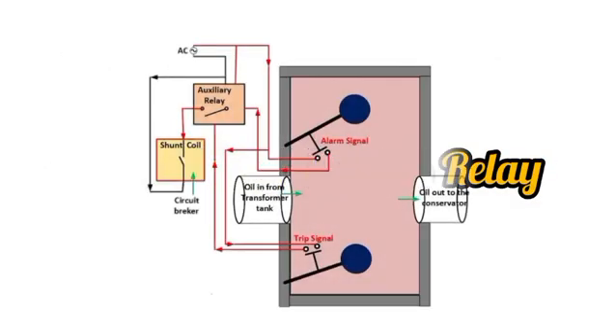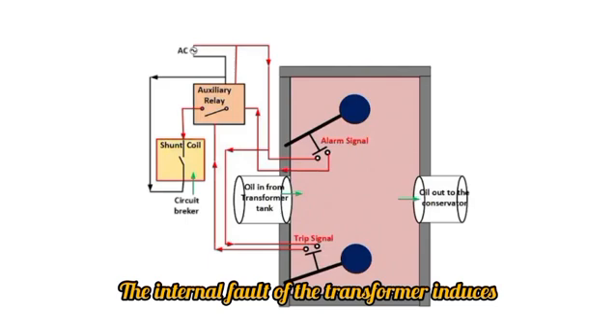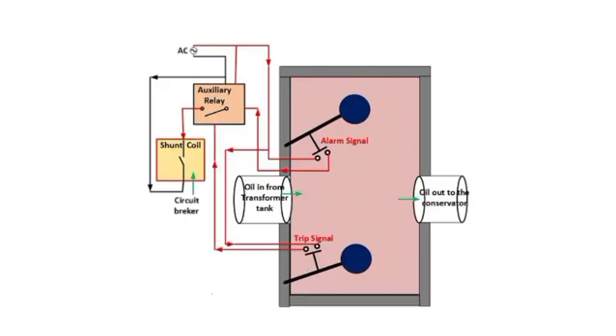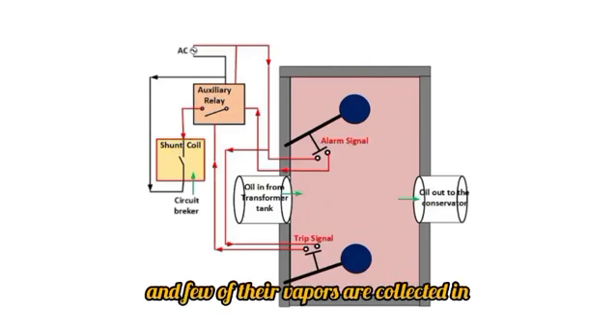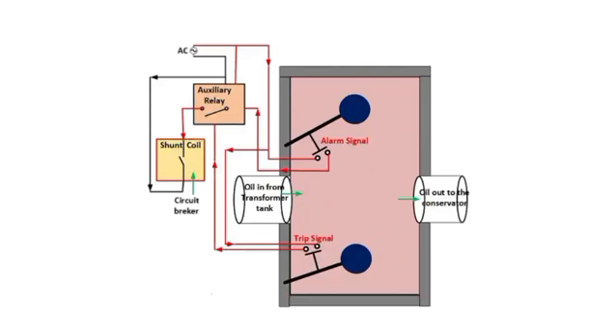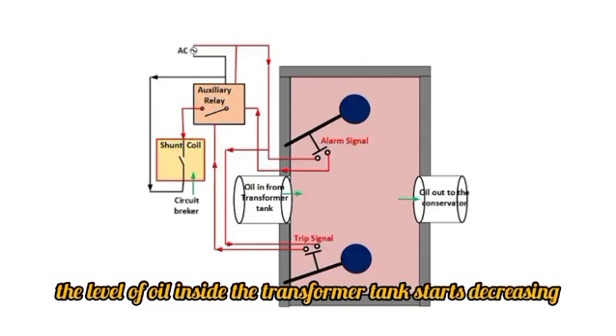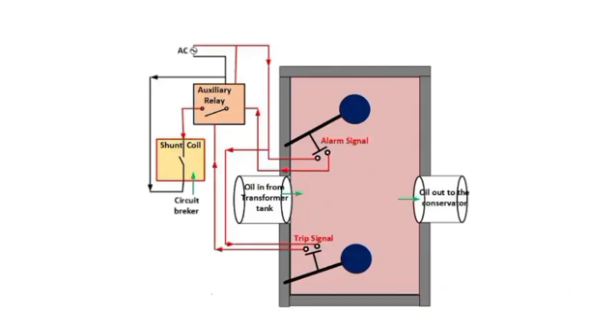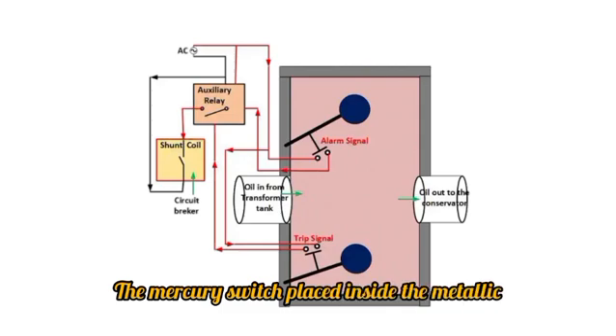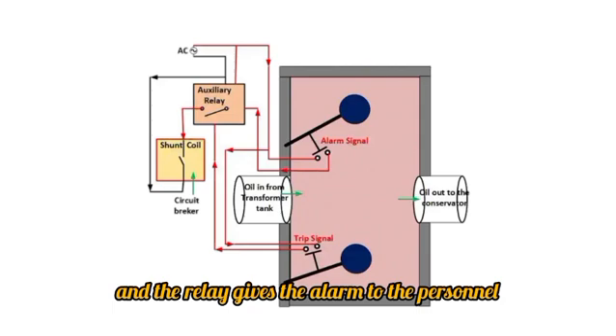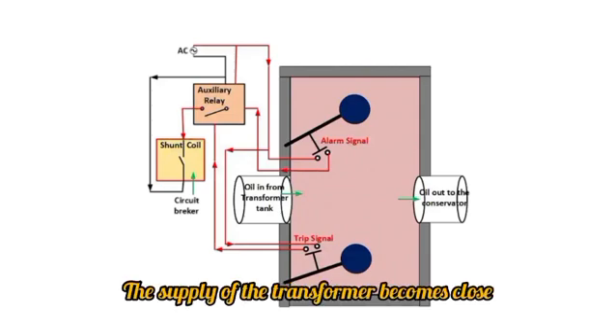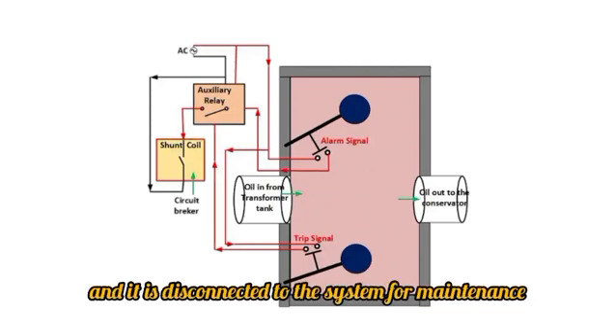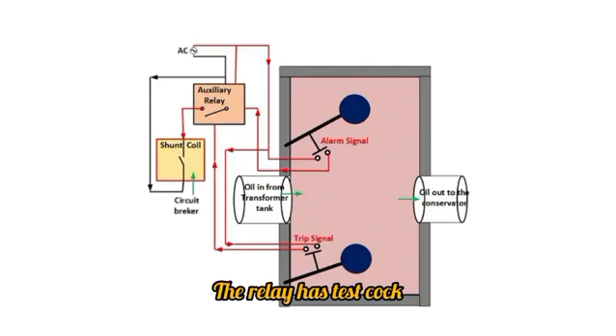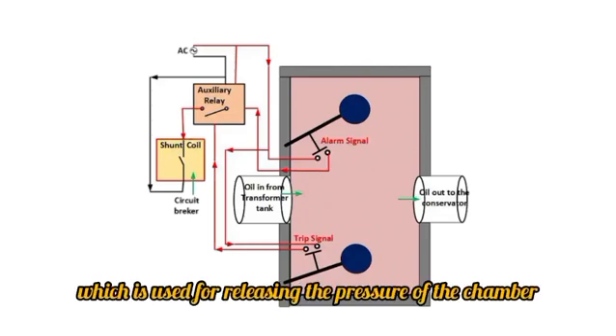Operation of Buchholz relay. The internal fault of the transformer induces an arc inside the main tank. The oil of the transformer starts heating because of the thermal effect. The gas moves upwards, and some of the vapors are collected in the upper area of the main tank. Because of the evaporation, the level of oil inside the transformer tank starts decreasing. The mercury switch placed inside the metallic chamber becomes tripped, and the relay gives the alarm to the personnel. The supply of the transformer is closed, and it is disconnected from the system for maintenance. The relay has a test cock which is used for releasing the pressure of the chamber.